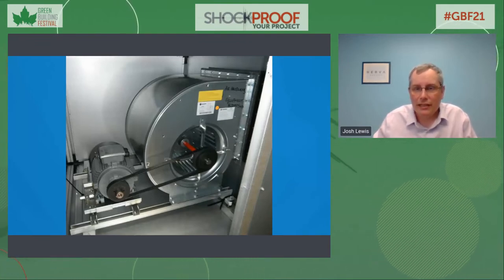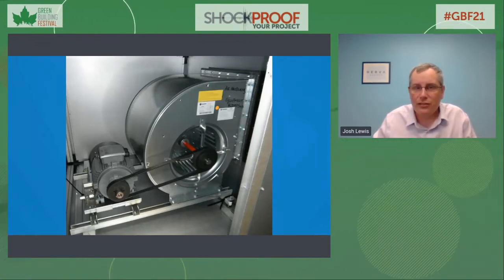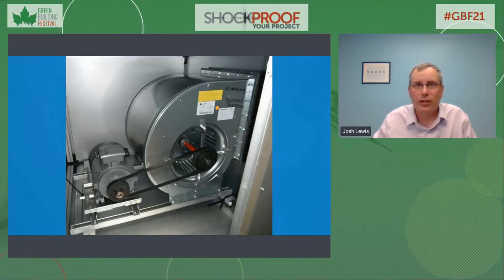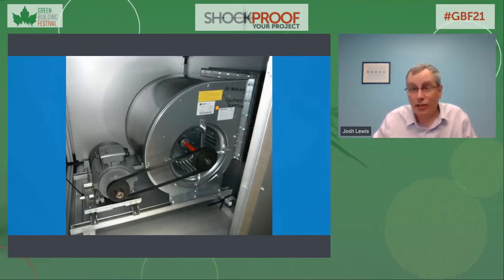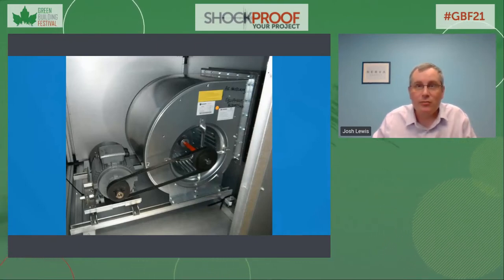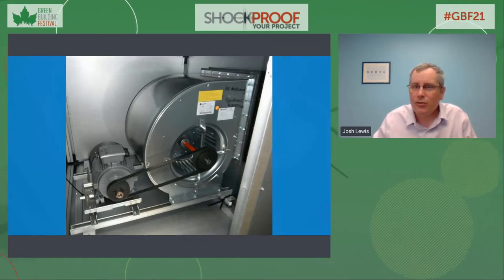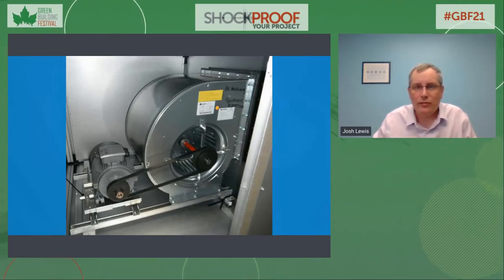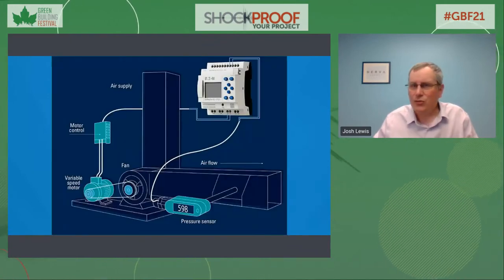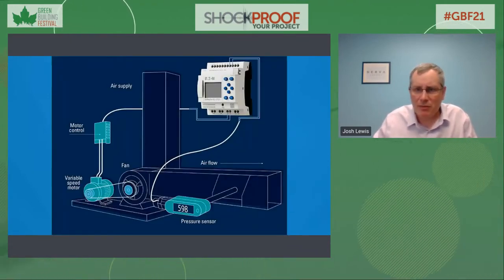The typical way that the operation of the fan is changed and tracked is through HVAC controls, also known as building automation systems. By installing, upgrading, or retrocommissioning the controls, the fan operation can be set up to provide the air circulation needed when the building is occupied, while reducing the energy waste by turning the fans off during unoccupied periods. Next, is the fan running at its maximum capacity?